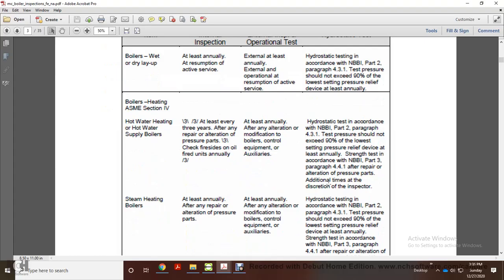Alright, boilers under the American Society of Mechanical Engineers Section 4, hot water heating and hot water supply boilers: inspection at least every 3 years, and after every repair or alteration of pressure parts. Check fireside. Annual operational test, at least annually and after alteration or modification of boilers, equipment, or auxiliaries. Hydrostatic test in accordance with NBBI paragraph 431, 90% of lowest setting of the pressure relief device, at least annually. Strength tested in accordance with NBBI Part 3, paragraph 441.